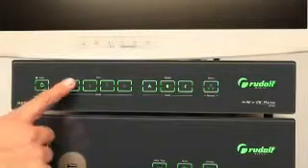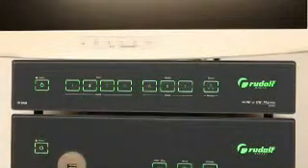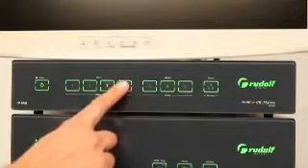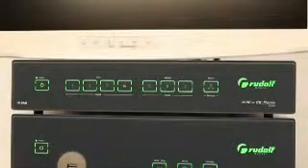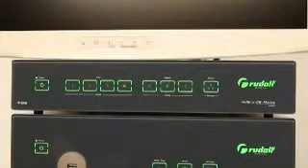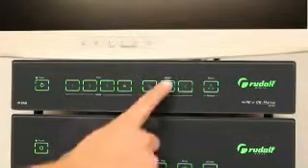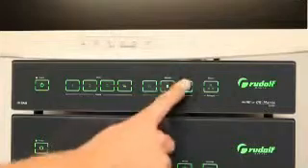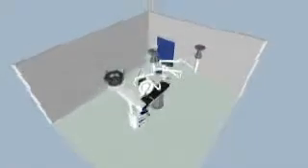The OR matrix allows various image sources to be included in the system, for example endoscopic cameras, operating theatre light camera and operating theatre ambience camera systems, or additional camera systems, for example flexible video endoscopes, and to distribute them to the monitors connected to the system, for example ceiling lights or operating theatre lamps. This allows the surgeon and the entire team an ergonomic way of working in the operating theatre and ensures that all images required for the operation are available.